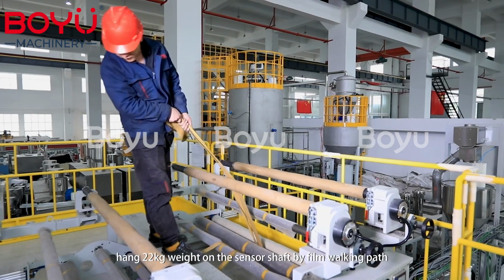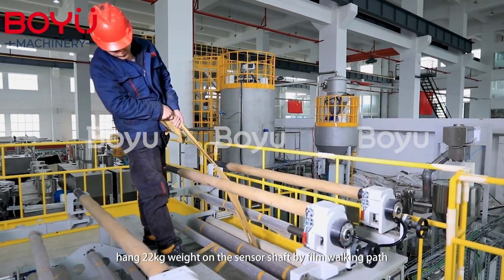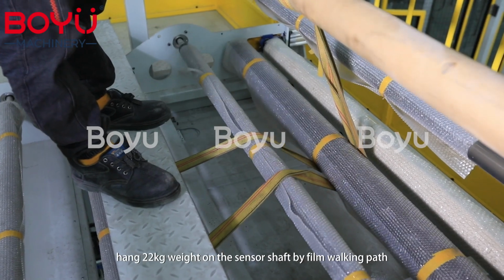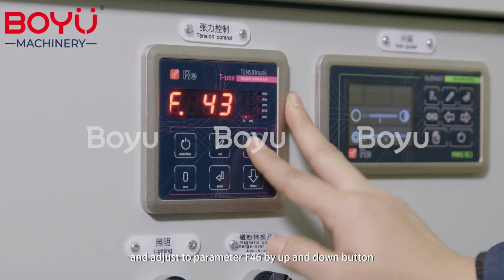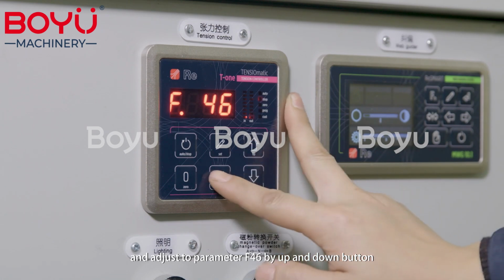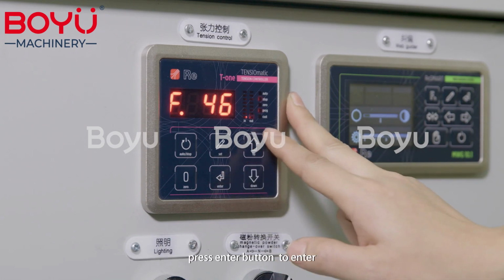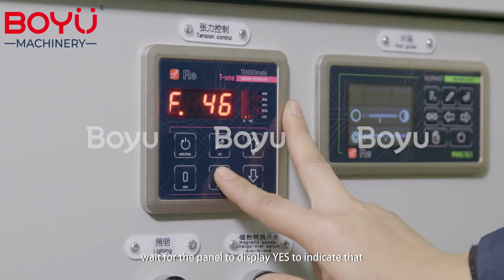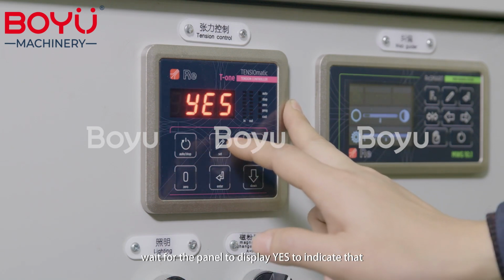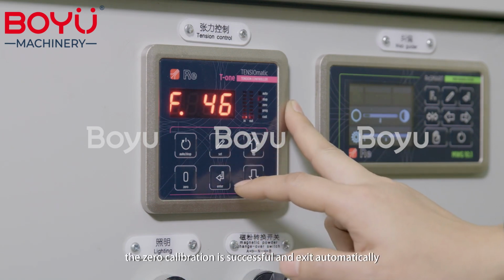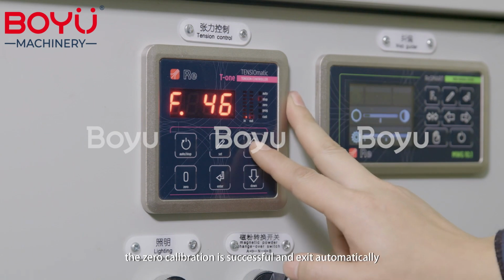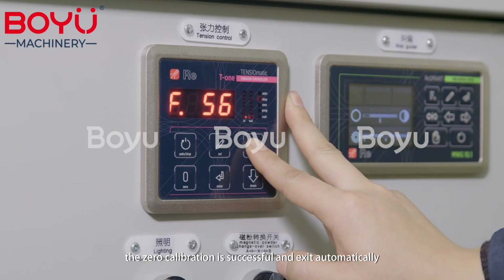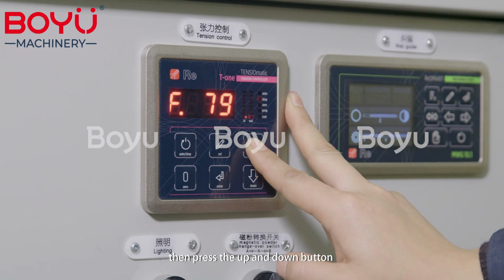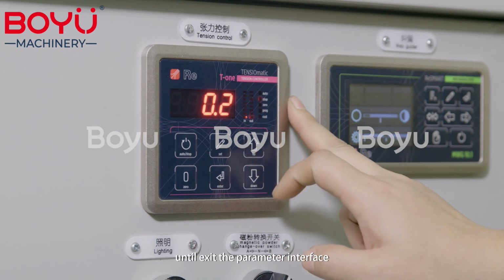Hang 22 kilograms weight on the sensor shaft by film walking path and adjust to parameter F46 by up and down button. Press Enter button to enter. Wait for the panel to display Yes to indicate that the calibration is successful and exit automatically. Then, press the up and down button until exit the parameter interface.